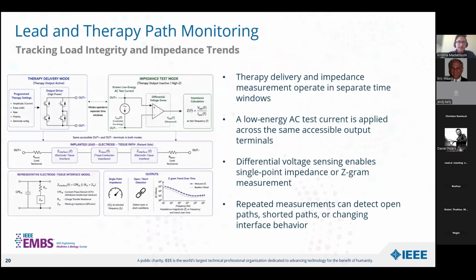Looking at the lead and therapy path monitoring, the key question here is whether the electrical path from the device to the lead or the electrode is still behaving as expected as time passes. The important point is that the therapy delivery and impedance measurement operate in some kind of windows. During normal therapy, the output driver can deliver the programmed stimulus through the output terminals. And during the diagnostic phase, we can use the same terminals to do some kind of impedance measurement of that electrode.